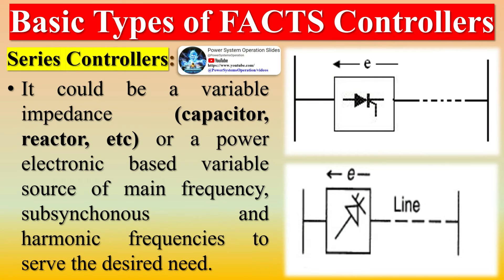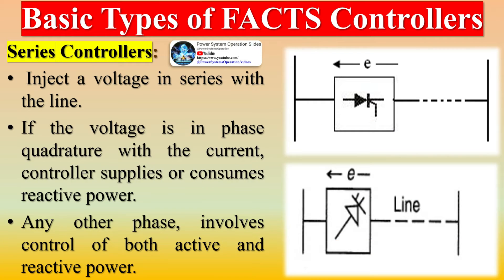FACTS can be described as a collection of controllers like phase shifters, static VAR compensators, etc. The major operation of the FACTS system is by varying the apparent impedance of a particular transmission line so that the flow of power can be improved over the required path. By controlling the impedance of the transmission line with electronic devices, a constant power flow in the required path can be achieved. The power flow can be maintained in case of any variations in load levels or any contingencies.